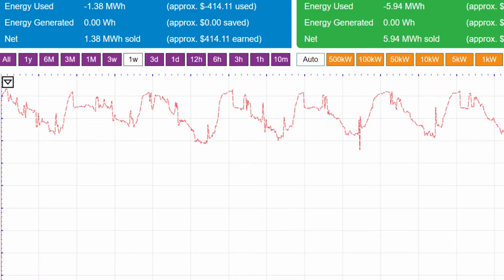All right, what we're looking at is an eGauge. And if it's possible to scroll a little bit to the right so we see the graph marks, what this shows is 1 week of operation, 24 hours a day. Those valleys that you see represent around 3 or 4 in the morning, and those peaks, it looks a lot like the solar duck curve, or the PV curve, and it actually exactly mirrors it.